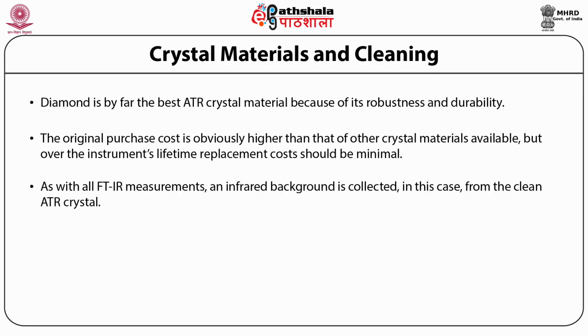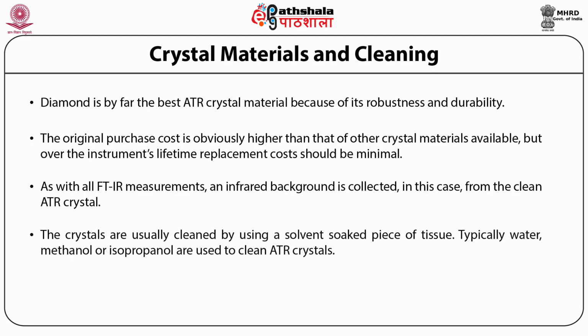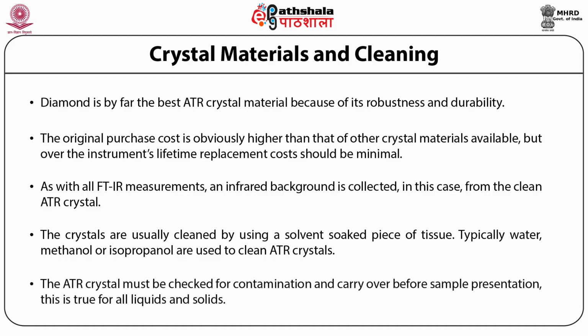As with all FTIR measurements, an infrared background is collected. In this case, it is collected from the clean ATR crystal. The crystals are usually cleaned using a solvent-soaked piece of tissue. Typically, water, methanol, or isopropanol are used to clean the ATR crystal. The ATR crystal must be checked for contamination and carry-over before sample presentation. This is true for all liquids and solids.